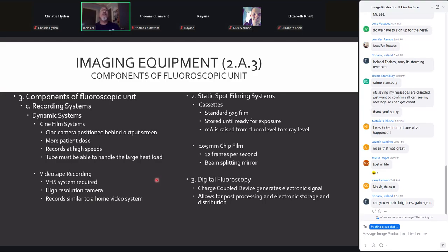The recording systems for fluoro and our dynamic systems, we could use Cine film. The camera was positioned behind the output phosphor, and we would use lenses and mirrors to split the signal from the output phosphor between the television camera tube and the Cine camera, so it would be off to the side of the image intensifier tube. This did lead to more dose to our patients, but it was capable of recording at high speeds, similar to a movie, because it did so with multiple small frame images, it was actually like a film tape.